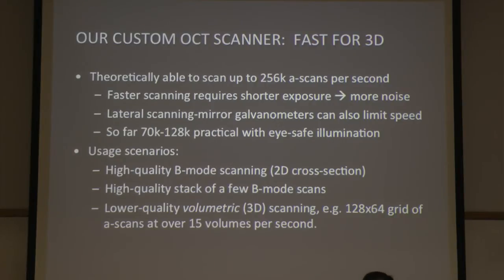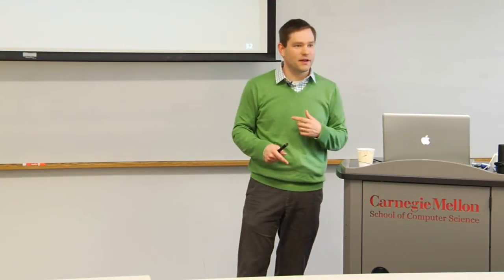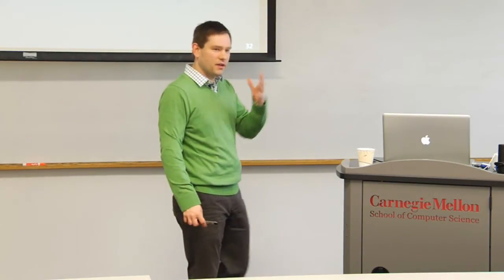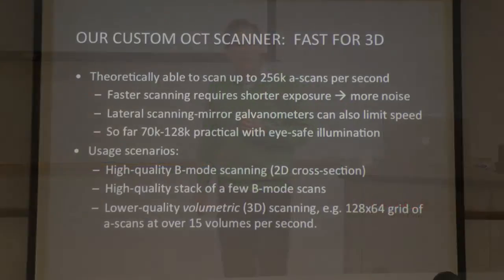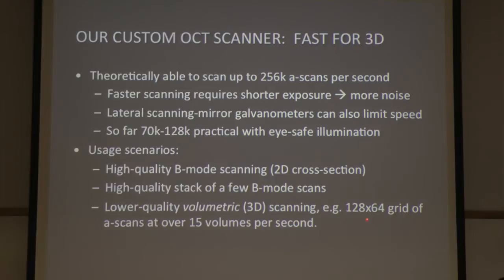Additionally, unlike diagnostic systems, which have a focus on image quality, and it doesn't matter if the patient sits still for half a second while you acquire a 2D cross-section image, in our case, we want to be doing 3D visualization, pulling out cross-sections. We want to be imaging volumes in real time. To do that, we used a unique arrangement with a custom repurposing of a high-end line scan camera and some tricks with other special software and hardware to produce a system that, at eye-safe illumination levels, so it's not going to harm the patient, can image at a 128 kilohertz A-scan rate, which translates to basically being able to do a 3D scan of 128 by 64 pixels in the transverse plane and 1,024 pixels in depth for an entire 3D volume.